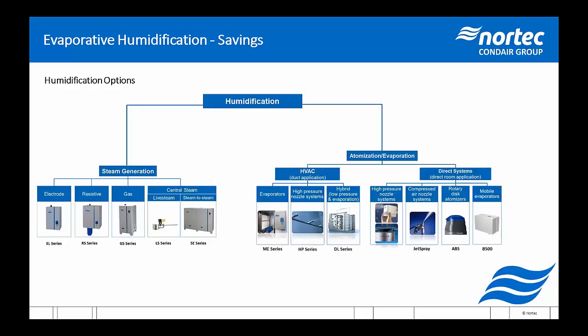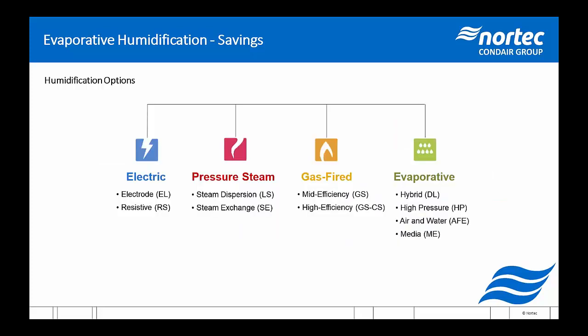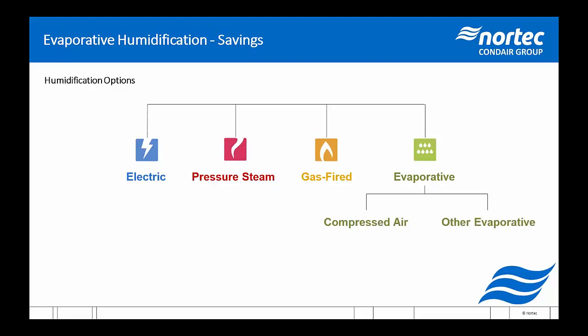So to start, I like to put this slide up almost as a look how many things we can do slide. There's quite a few options when it comes to humidification, but they typically break down to electric, boiler steam, gas-fired steam, or evaporative humidification. And we can remove the names of the products and the different styles there and end up just with the four main ones, and then evaporative can be split into compressed air, ultrasonic, and other evaporative technologies. And this sort of breaks it down in a way where we can see the different costs between each technology or each type of humidification.